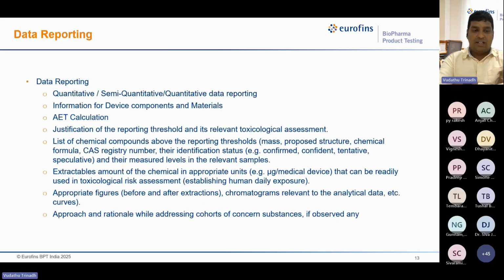And coming to data reporting, qualitative, semi-quantitative, or quantitative data reporting should be required. Information for device components and materials should be captured. And AET calculation along with its justification is required. Justification for the reporting threshold and its relevant toxicological assessment, if anything, shall be captured. For the list of chemical compounds observed above the threshold limits, any proposed structure or CAS number, or its identification status like confirmed, confident, or tentative, shall be captured along with the quantification levels at which it has been determined.